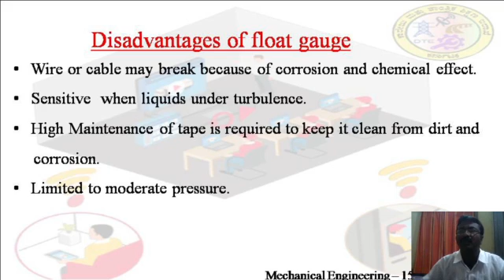The next disadvantage is the float gauge is limited to moderate pressure. That is, float gauge cannot be used for high pressures. The next disadvantage is the float gauge has limited range. That is, if the tank is of more height or depth, the length of the rope or cable becomes more. If the rope length exceeds 1.2 meter, then the device becomes bulky and it is difficult to balance the cable on both the sides.